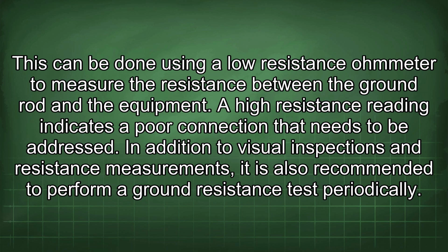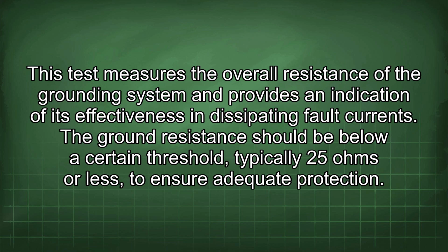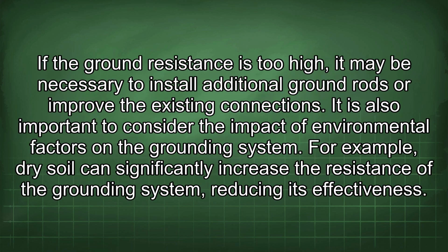In addition to visual inspections and resistance measurements, it is also recommended to perform a ground resistance test periodically. This test measures the overall resistance of the grounding system and provides an indication of its effectiveness in dissipating fault currents. The ground resistance should be below a certain threshold, typically 25 ohms or less, to ensure adequate protection. If the ground resistance is too high, it may be necessary to install additional ground rods or improve the existing connections.